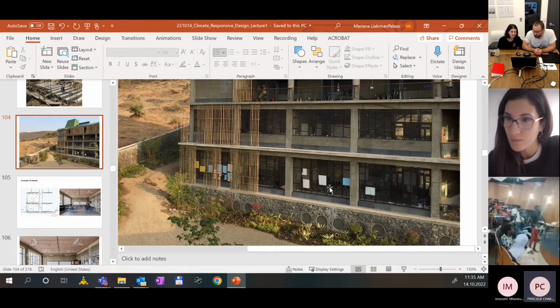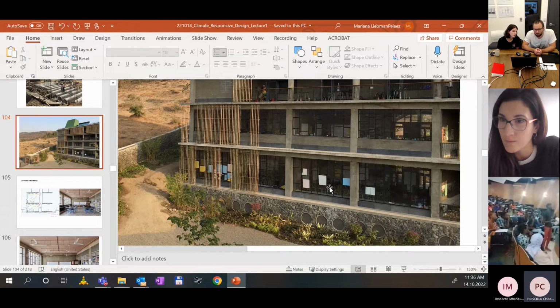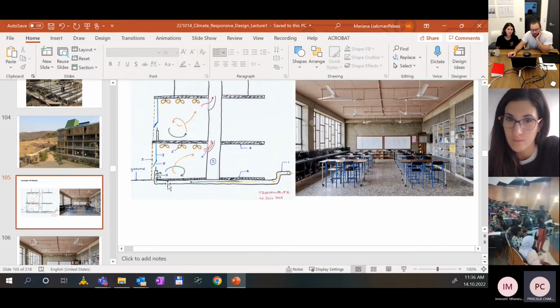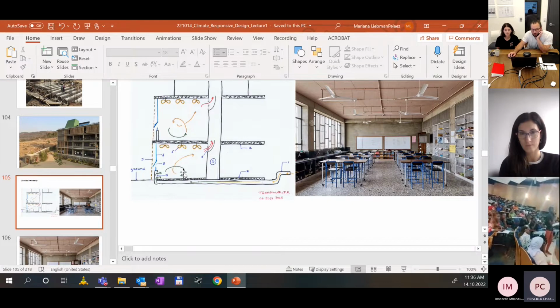Good day. Another question which is imposed while you're explaining: in that air duct, doesn't it seem that the lower part must be colder than the upper part, as it is just a simple mechanism of basic air, not using any mechanical system? I'm not 100% sure I understood correctly, but yes, the earth duct is not using any mechanical system, but you need this chimney to exhaust it. You need the height difference, and you also need the temperature difference. Otherwise, this will not run naturally. If it were just a room without the exhaust, there would not be enough temperature difference and height difference to drive this ventilation naturally.